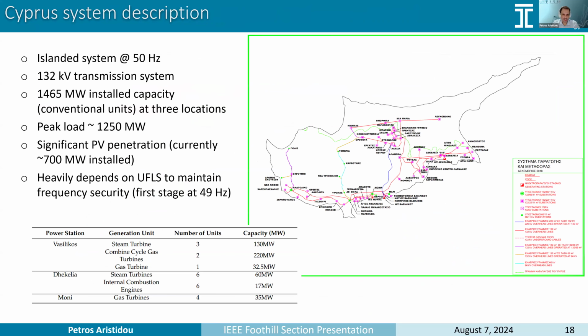In Cyprus, this is a very strange situation because, as I said, there were 3 areas of generation. I don't know, you can see my mouse, right? Yes, I can see. Okay, so there were 3 areas of generation here. And now they are moving into a single point of generation in this area, in the Vasilikos area. So the other 2 are being gradually abandoned. And then we have the situation where the fault levels in this area are actually increasing because we're moving all the synchronous generation to this area, while the remote locations are decreasing. And that's where we saw this up to 40% reduction in the fault levels.